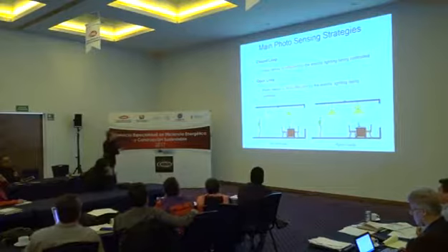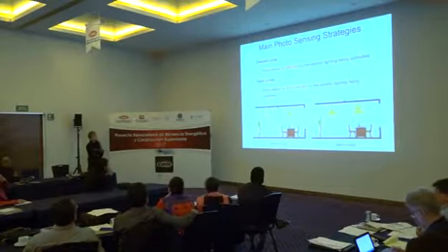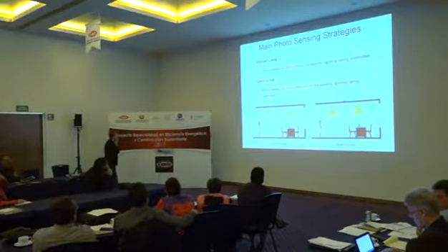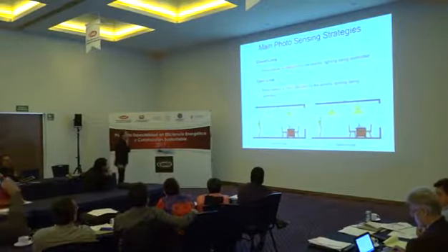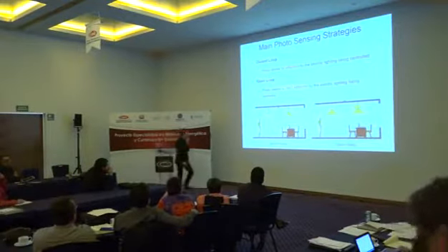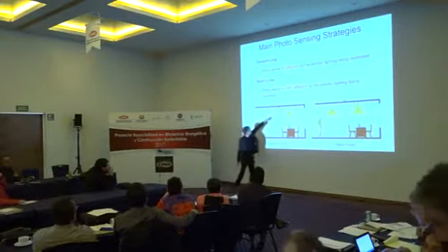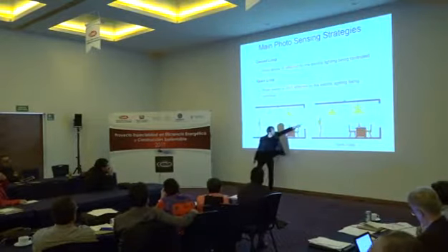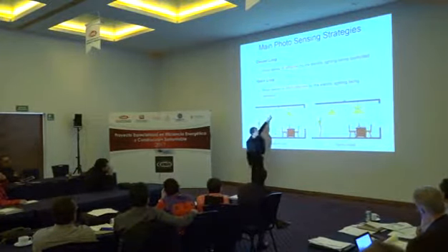Okay. Two basic approaches to doing that. There's an approach called closed loop and open loop, and this is what you'll hear in the daylighting industry. Closed loop, the photosensor is affected by the light that it's seeing. So closed loop, it's looking inside. It makes decisions based on the available daylight. It sees the electric light.